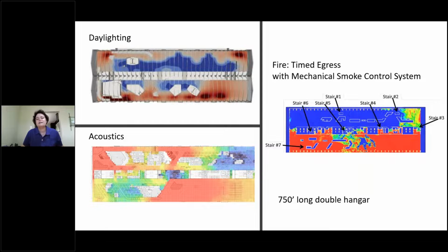Then we had to do a bunch of timed egress and smoke control analysis with our fire engineers, to look at, once we turn on all those smoke exhaust fans for the smoke control system, how long it takes for people to get off the 4th floor, down through the building, and out. Because this is a giant double hangar that's 750 feet long — a gigantic smoke control system in that space.